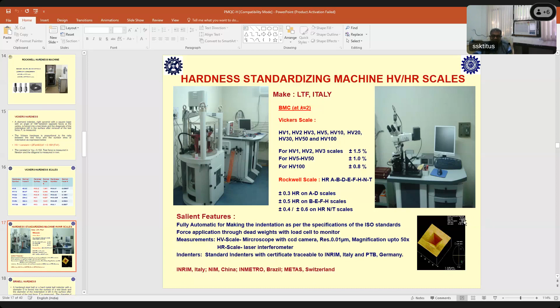The microscope and the interferometer, whatever you are using for measuring the depth or the diagonal, have to be calibrated. This particular machine has a laser interferometer, because it also has a Rockwell scale. For Rockwell scale we need to measure the depth, so we use a laser interferometer in this case. For the Vickers scale, we use the microscope with a CCD camera, with 50x magnification and a resolution of 0.01 micron. We used this machine even for the intercomparison in the Rockwell scale, and this kind of machine is used in several NMIs, not only in India but also in Italy, Brazil and Switzerland.